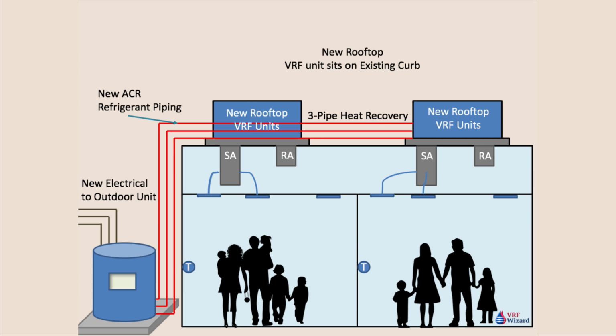It allows you to use the existing curbs, which is a real benefit. So this is a little less costly than a traditional VRF system, because now you don't have to worry about locating the indoor units inside. You don't have to worry about running ventilation duct through the building. You don't have to worry about ASHRAE 15 in some of the smaller rooms, because all your ACR refrigerant piping is now run on the outside of the building. Your outside air is now accessible from your rooftop VRF unit.